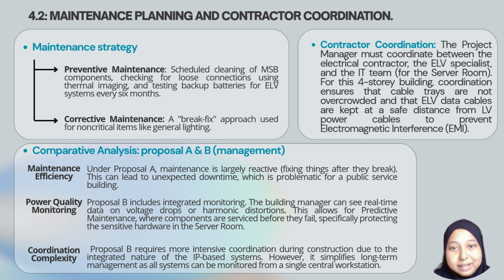4.2 is about maintenance planning and contractor coordination. A building's lifespan is determined by how well it is maintained after the initial handover. First, the maintenance strategy is preventive maintenance, which is scheduled cleaning of MSB components, checking for loose connections using thermal imaging, and testing backup batteries for the ELV system every 6 months. Next is corrective maintenance, a break-fix approach used for non-critical items like general lighting. So next is contractor coordination, where the project manager must coordinate between the electrical contractor, the ELV specialist, and the IT team for the server room for this four-story building.